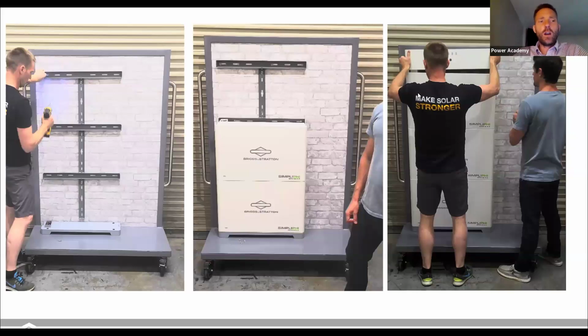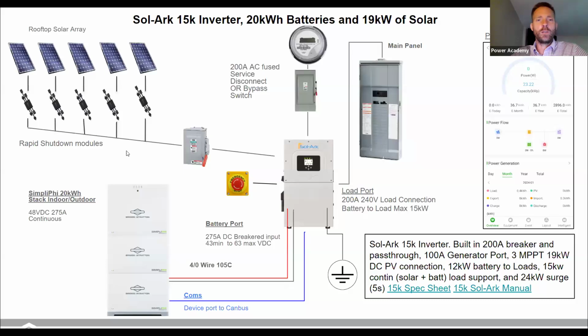So the mounting of this battery does have a rack, and that rack is there to prevent that battery from tipping over, but it is essentially invisible by the time you've completed the installation. It's hidden with side plates, etc. The installation itself goes very fast. The installation I'm doing here on just this training cart took about 7 minutes to fully assemble the entire battery. On a real job site, you're looking at probably 30 minutes once you get that wall mount set up, etc. But it's a very fast installation, given the rapid stack connectors that Briggs & Stratton has brought to market here.